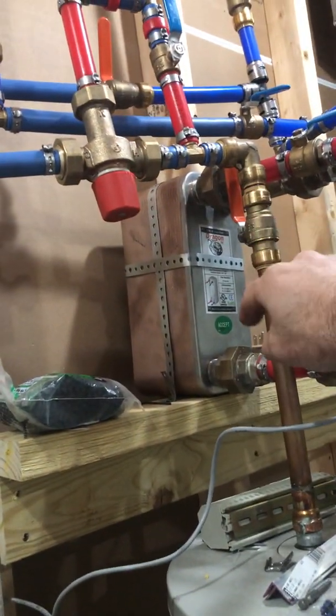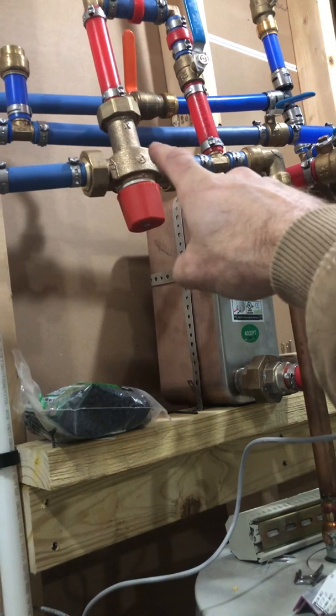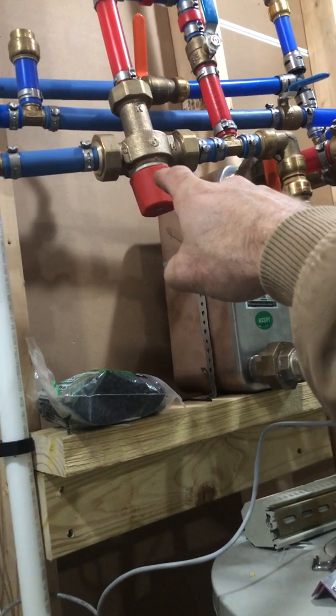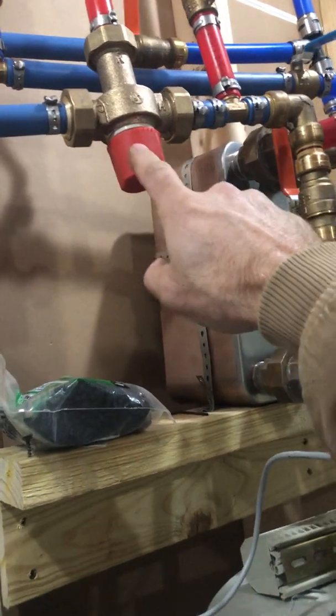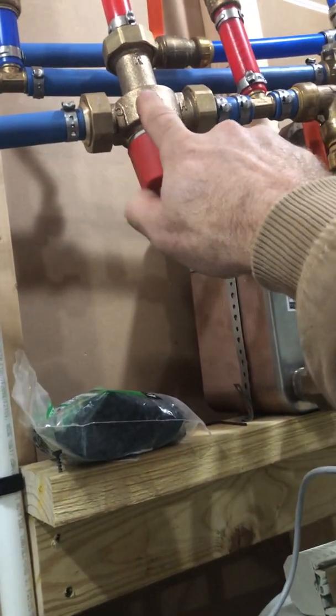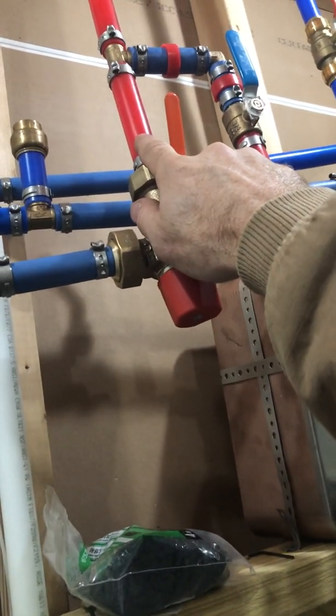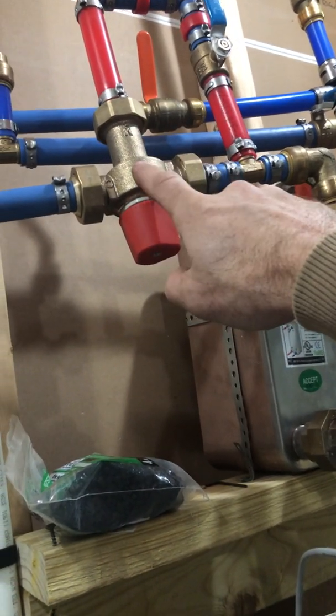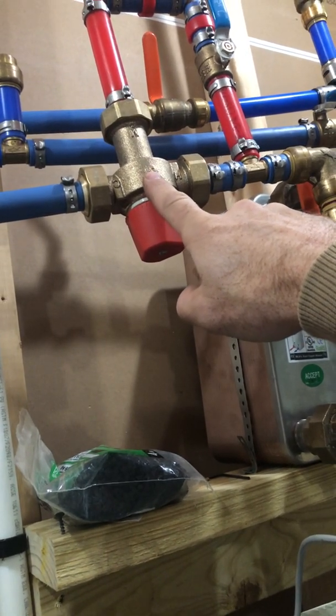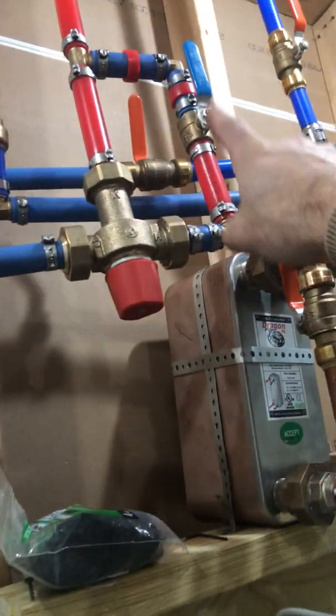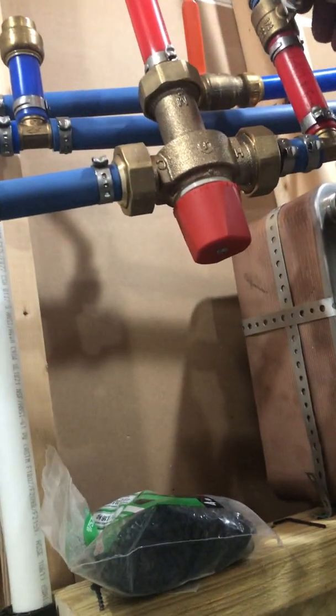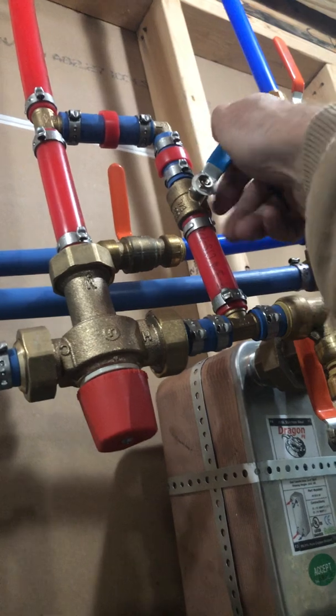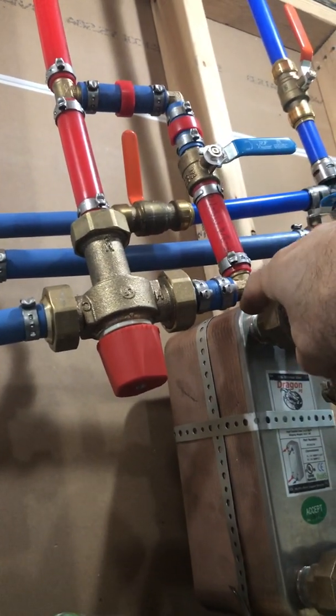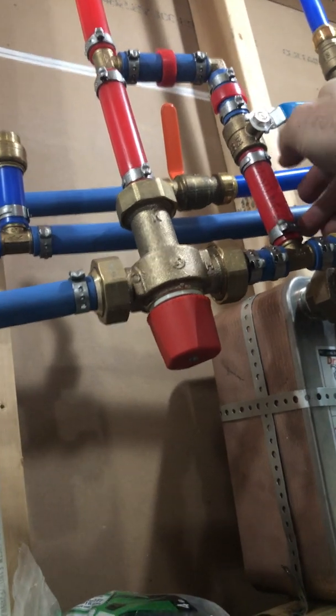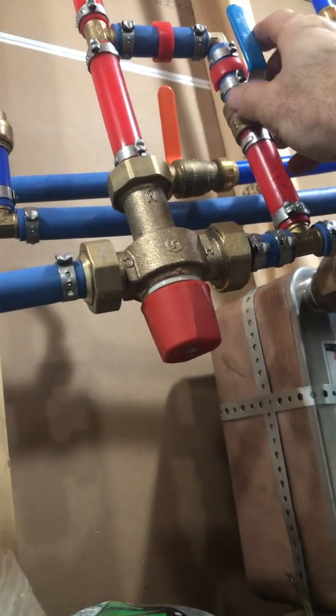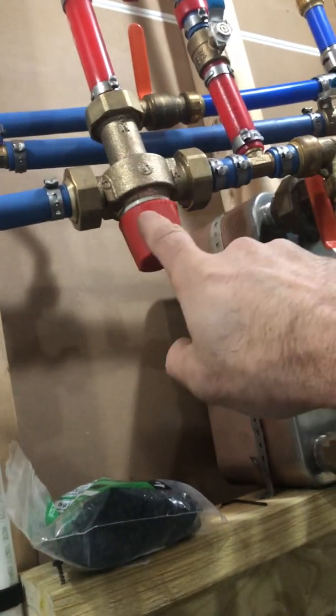So as the hot water comes out here, I'm adding in a mixing valve for that hot water. When the boiler is running, it will mix it back down to, say, 130, and send it on up your hot water line. When the boiler is not running, then it really doesn't matter. I've got this bypass here. When the boiler is running, I'll be able to just close this bypass. It'll force all of the hot water through the mixing valve. And when I don't run the boiler in the summer or whatever, I'll just be able to open that up, and I don't have to mix that here.